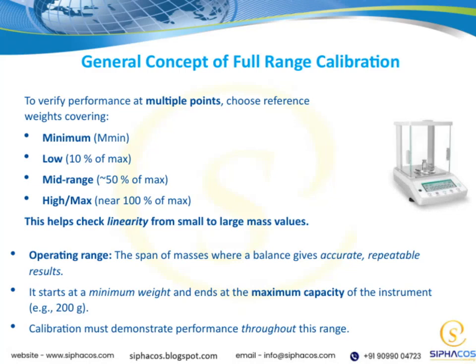Let's talk about the operating range of a balance. This is essentially the span of masses where the instrument can give accurate and repeatable results. It starts at the smallest weight you want to measure, what we call the minimum weight, and goes up to its maximum capacity, like 200 grams in this example. When you're calibrating, it's important to demonstrate that the balance performs well throughout this entire range, not just at a single point.